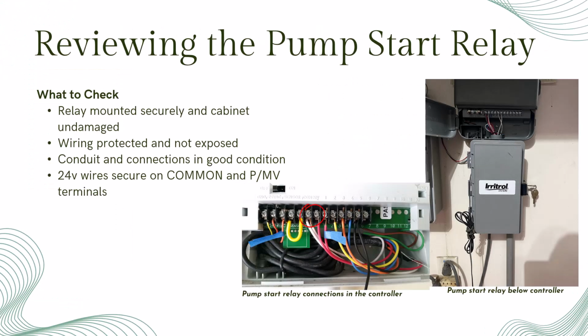A pump start relay allows the controller to turn the pump on and off automatically, so the inspection here is quick but important. I make sure the relay cabinet is secure, not cracked, and that the wiring is protected, ideally in a conduit leading back to the controller. I also check the conduit and connections where the relay ties into the pump and controller. Finally, I verify that the two 24-volt wires are firmly attached to the common and the P/MV terminals inside the controller. Just a few simple checks can prevent nuisance pump failures and service callbacks.